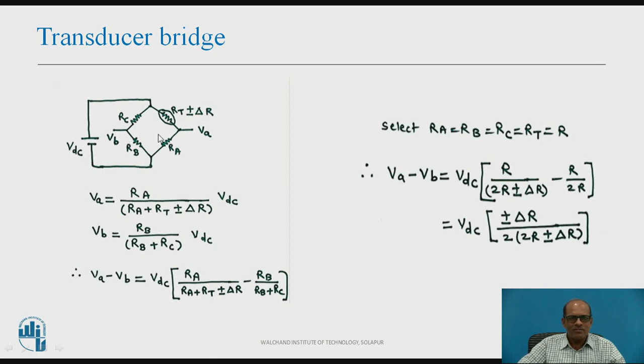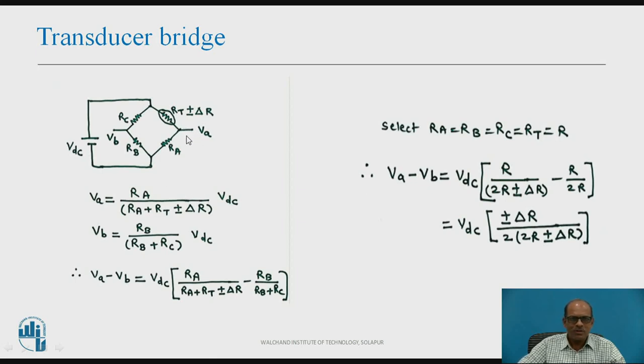The voltage generated between points A and B, which is V A minus V B, is given by: V A − V B = V DC × (± delta R) / (2 × (2R ± delta R)). This means V A minus V B is directly proportional to the change in resistance, and change in resistance is directly proportional to change in temperature because the characteristics of PT100 are linear. Hence the differential output of this bridge is directly proportional to temperature.